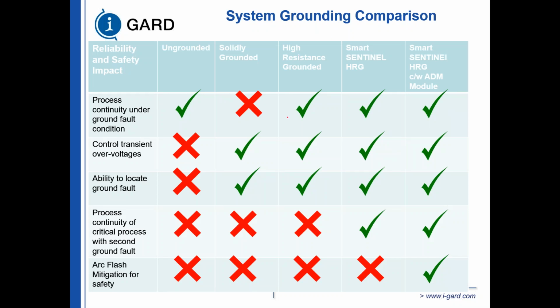So to summarize, with an ungrounded system, you get process continuity under ground fault conditions. You're not going to get that in a solidly grounded system. You're going to get control of transient overvoltages, yes, because when you have a ground fault, you're never going to have transient overvoltages. The ability to locate the ground fault, well, you want to trip the main breaker, and then you look for where the smoke is.